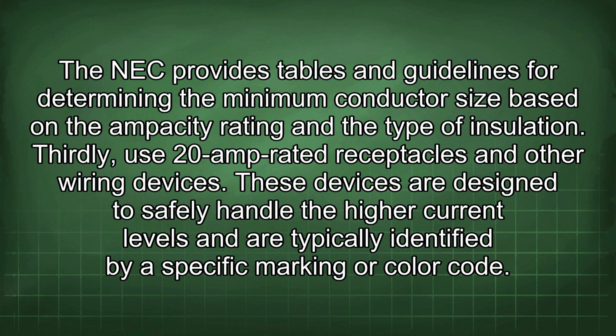Secondly, select the appropriate size conductors for the 20 amp circuits. The NEC provides tables and guidelines for determining the minimum conductor size based on the ampacity rating and the type of insulation. Thirdly, use 20 amp rated receptacles and other wiring devices.